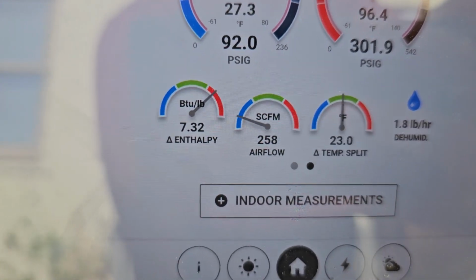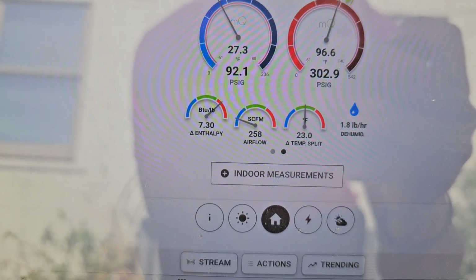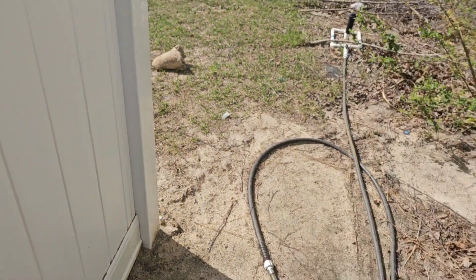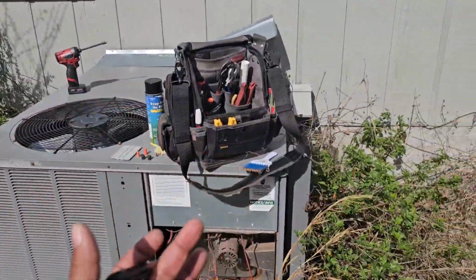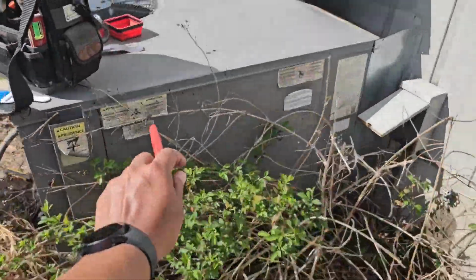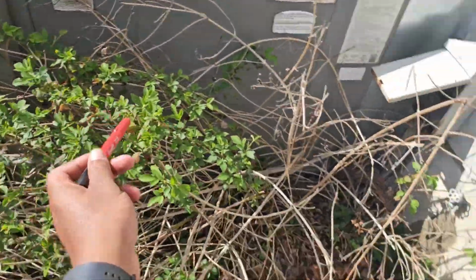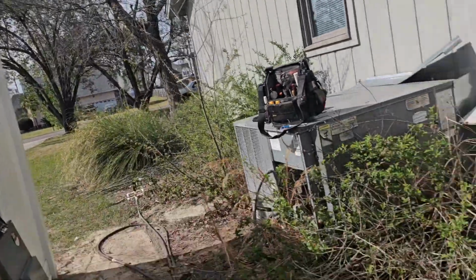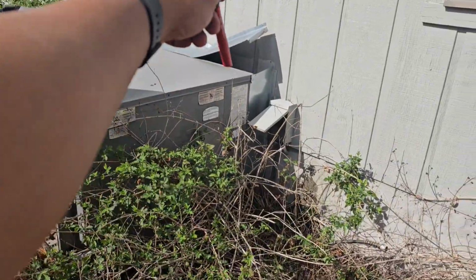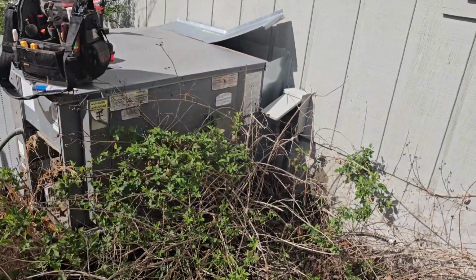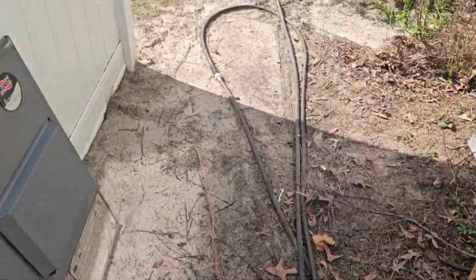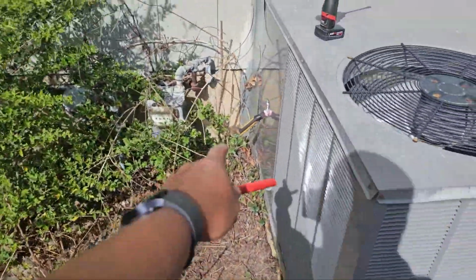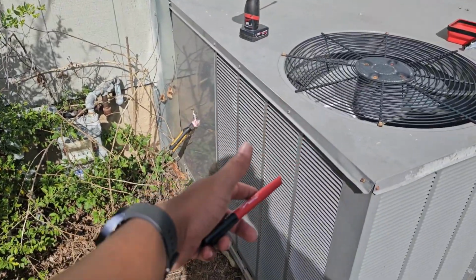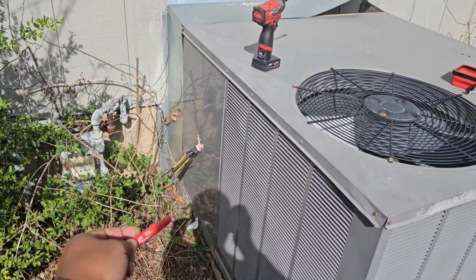Ah man, look at that airflow. Now I don't know how it's going to read the airflow based off of the Fieldpiece equipment, and how close I have my equipment to the fan may be interfering with that. Your blower motor on these Rheems sits right here, blows down into the heat exchanger and blows out that way. So with my probe face down into the square-to-round, it may be too close, and not necessarily directly in the airstream. Maybe it'd be a better representation if I had both of them in the square-to-rounds.